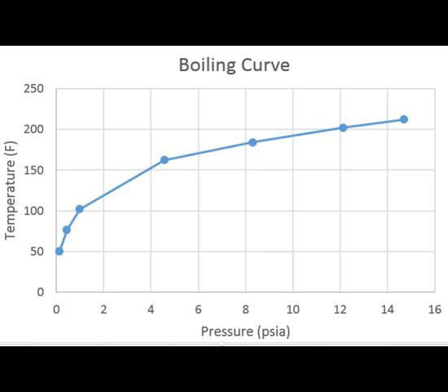So now you're probably wondering, well, if it's not boiling inside of the pump, then why do I care about all this crap anyway? Well, when the water finally reaches the impeller, the pressure will decrease even further on the low pressure side of the impeller. And if this pressure decrease is sufficient to get it to the boiling point, then it will flash into water vapor and will cavitate.